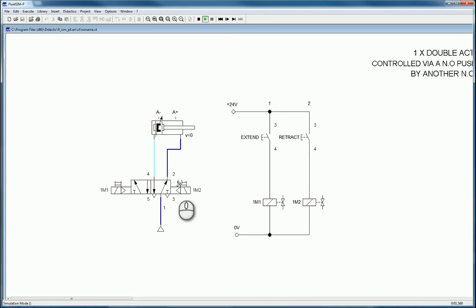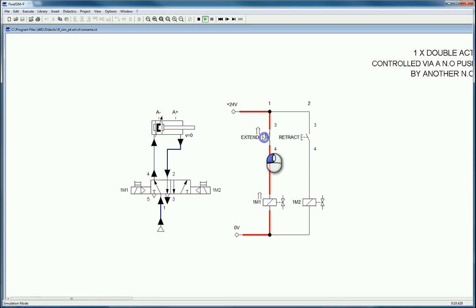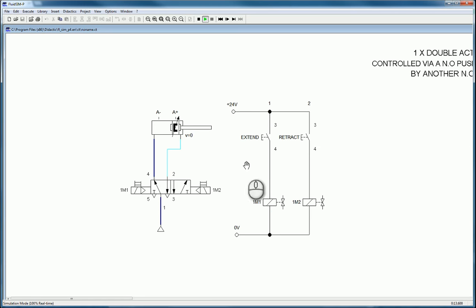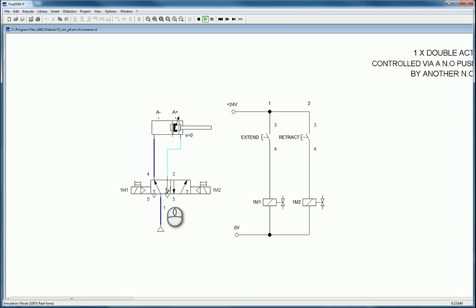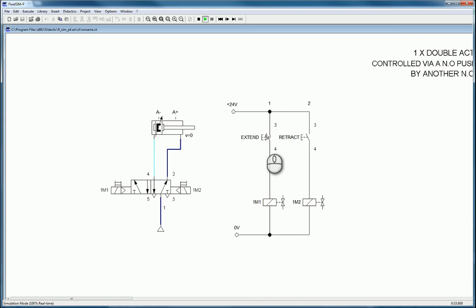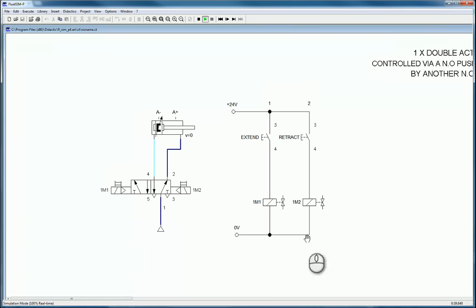Press play and you'll see that by default the air pressure causes the cylinder to retract. Press the extend button and even when you let go it stays in the same position, because it's a double solenoid valve — it doesn't spring back. It activates 1m1, which activates the valve solenoid, which sends air from port 1 to port 4, extending the cylinder. Press retract and the opposite happens, activating the other solenoid. This is called direct control.